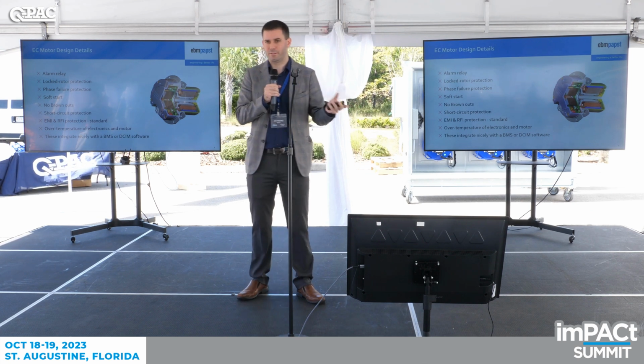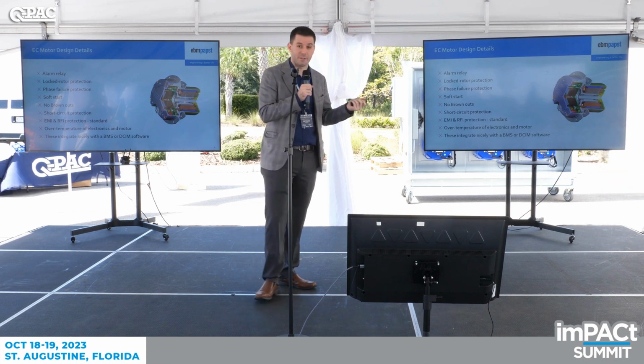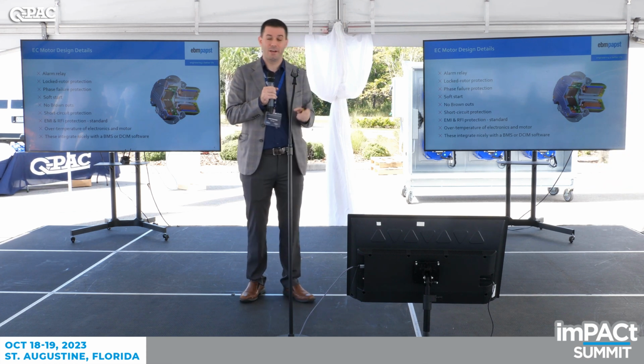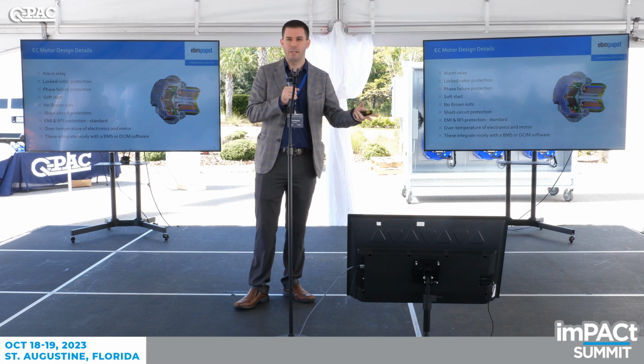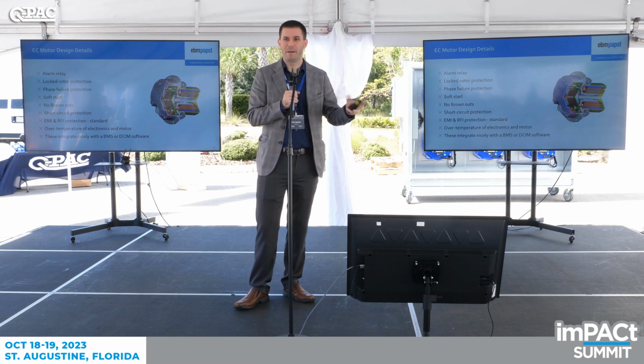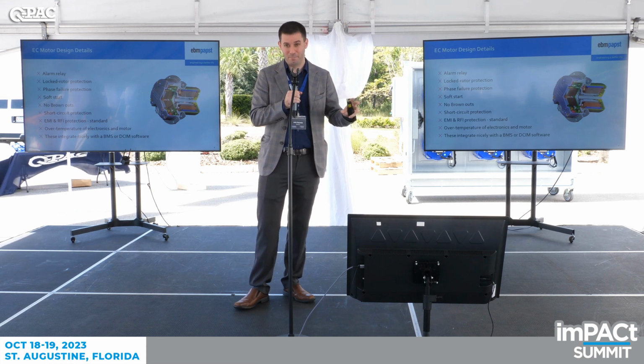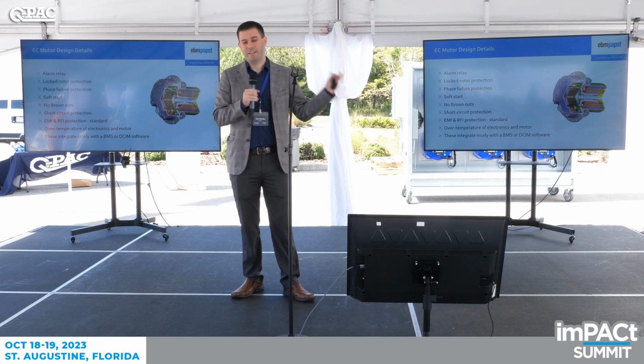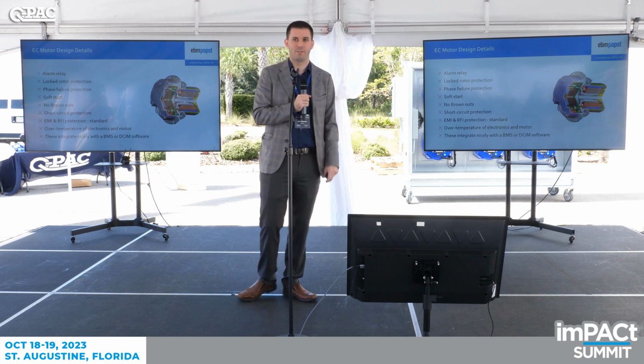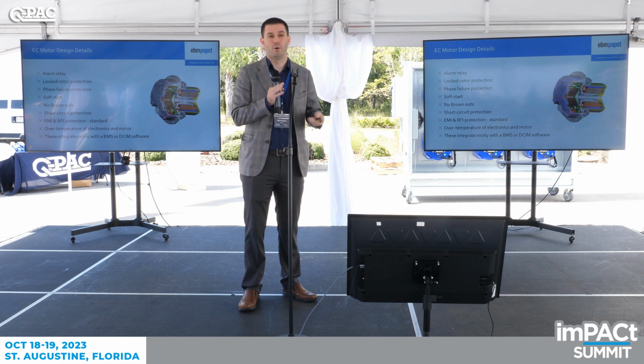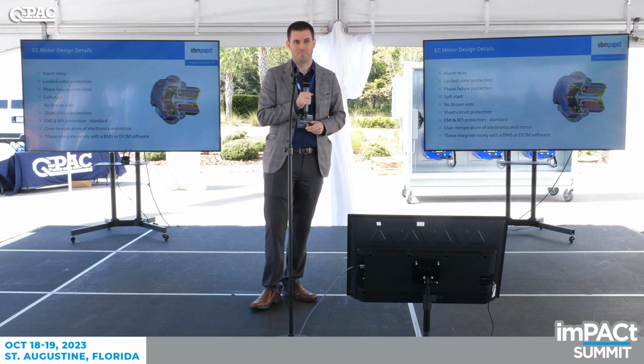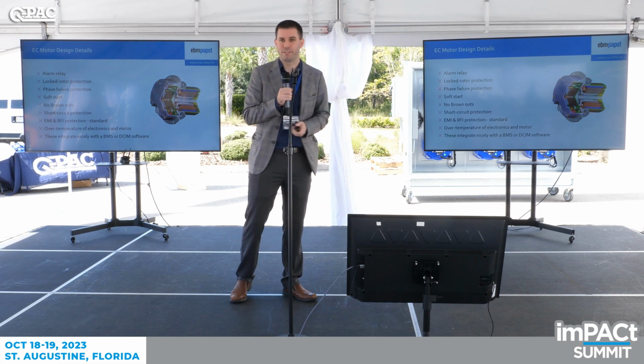And it'll just keep doing this until the alarm clears. What's nice is with the AC motor, the rotor's locked, and it just keeps on torquing up and heating that motor and damaging that motor, because you're adding heat into the bearing system, adding it into the windings, until it actually reaches a thermal trip, and that's what actually stops the motor from continuing to try and torque up.